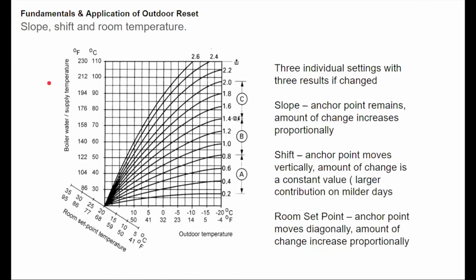Okay. Now, when we set it up, I've kind of thrown some terms out there in the setup, but in order to really tailor the heating curve, there are a few adjustments that can be made. And I'm going to actually work with our descriptions of our terminology: slope, shift, and room temperature. And all 3 of these are built in together to be able to tailor the comfort in the building. The first one I've thrown out a number of times is the term slope. You'll hear it referred to as the curve or the reset ratio.